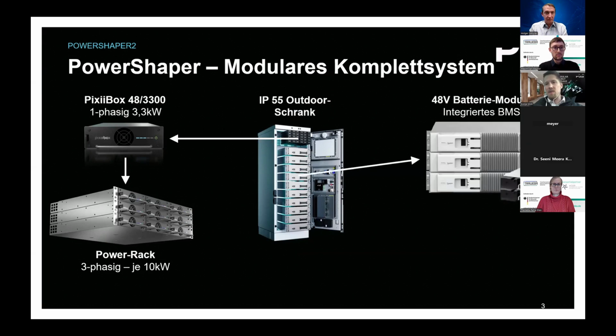In this cabinet, for example, we have a 50 kilowatt, 50 kilowatt-hour battery system. We use 48-volt batteries put in parallel, which is different from what you see in the market, but it comes from this telecom data center background. What we can build now is a battery system that at the same time can be a 48-volt uninterruptible power supply.